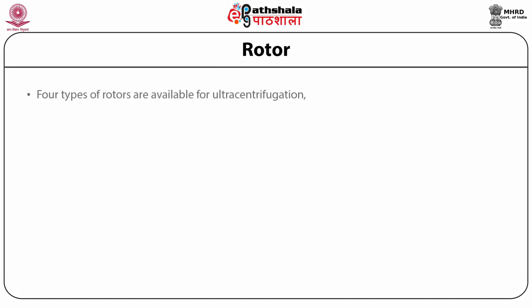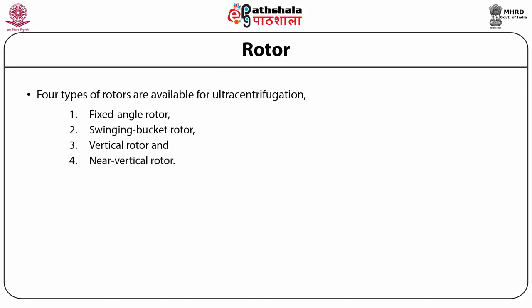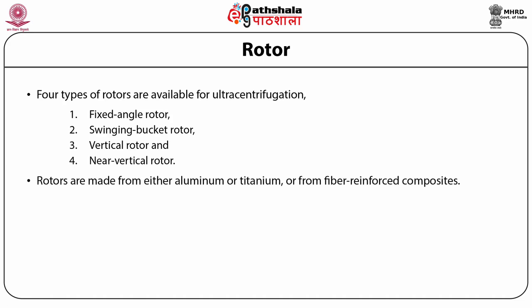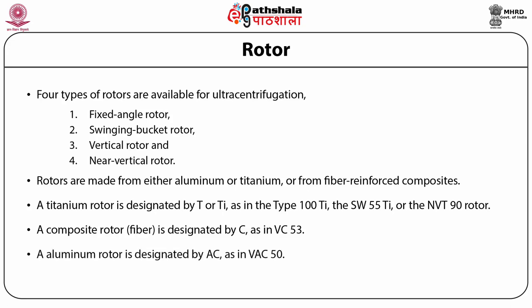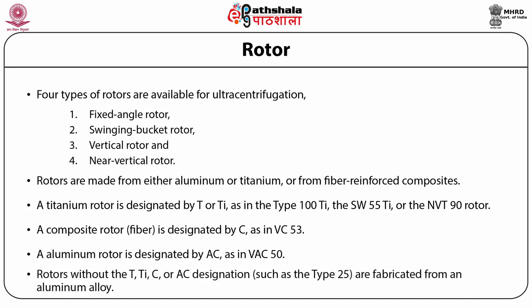There are four types of rotors: fixed angle rotor, swinging bucket rotor, vertical rotor, and near-vertical rotor. Rotors are made of either aluminum, titanium, or fiber-reinforced composites. Titanium rotors are designated with 'Ti' (e.g., Type 100 Ti or SW 55 Ti). Composite rotors are designated by 'C' (e.g., VC53). Aluminum rotors are designated by 'AC' (e.g., VAC50). Rotors without designation such as Type 25 are fabricated from aluminum alloy.